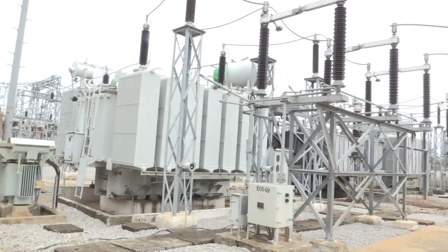During that, it undergoes some expansion and contraction, and then the insulation of the equipment is subjected to stress due to trippings and the nature of the faults associated with that type of transformer at the downstream. That's maybe why the consumers are experiencing issues.